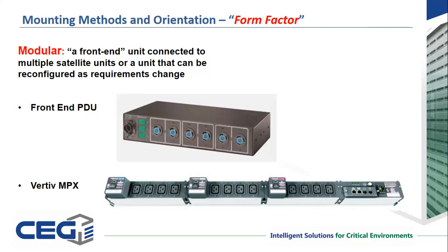It's tough to get someone to swap a power strip in a cabinet. It's tough to get someone to do a refresh with gear that's already up and running. But this thing lets you do hot swappable without removing the main power components of the power strip. So it's kind of cool in that regard. It is very expensive and it is physically large.